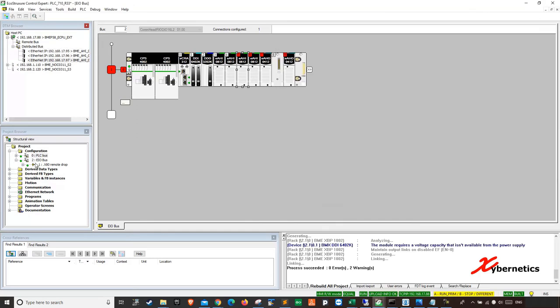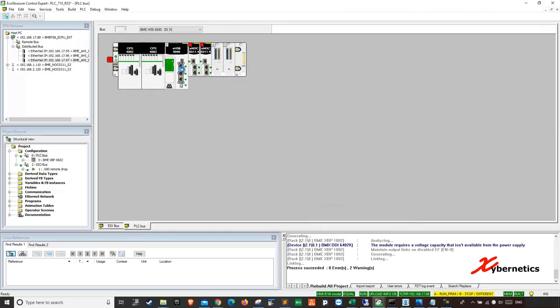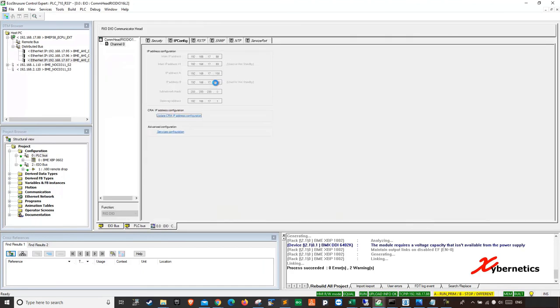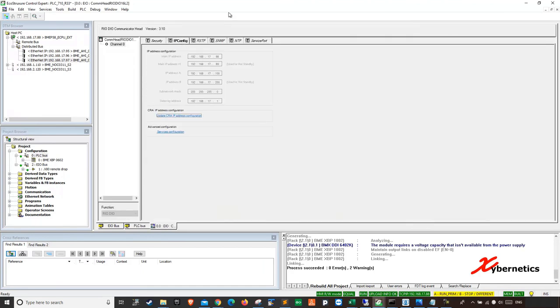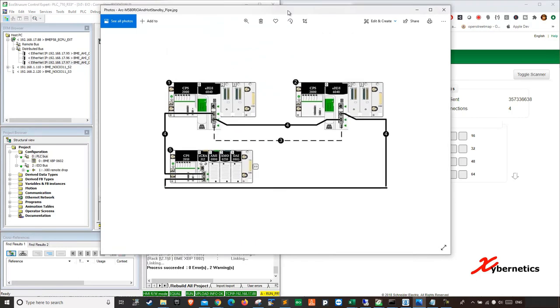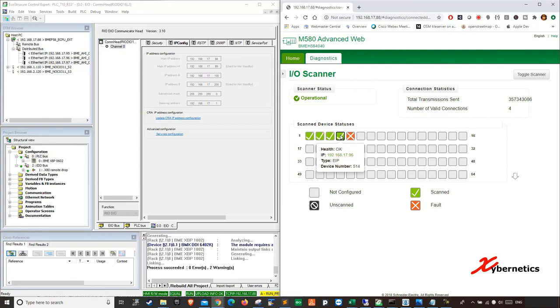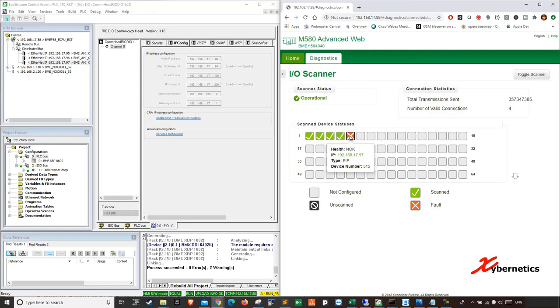If you click on PLC bus and click on this, it talks to IP config. So this is the IP address. So this is different from this, but they are under the same network. So this talks in a ring network, that IP address. Again, you know they've got three ports. The 100 is on this one. 88 could be anyone, 100 could be anyone. But for this ring, they're using 100.100 octet as your connection. So if you try to ping all of this, even this, the ping should respond, which indicates that your Ethernet connection and your configuration and your identifiers are all correctly set up.